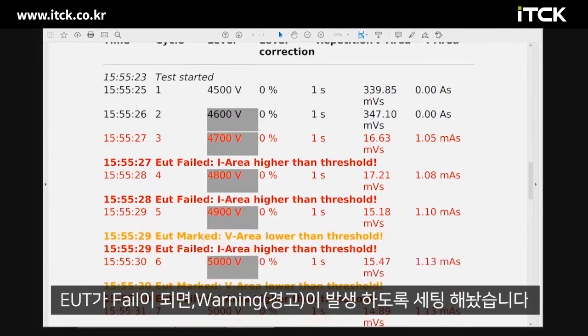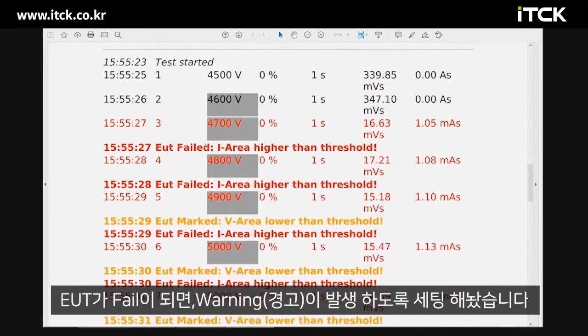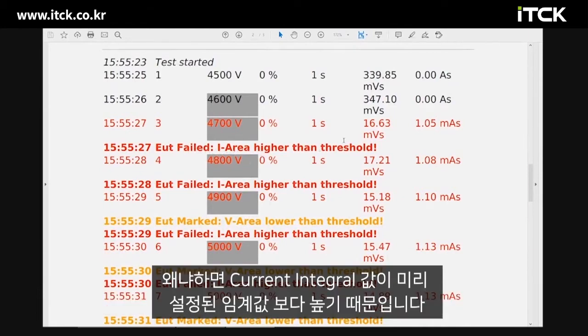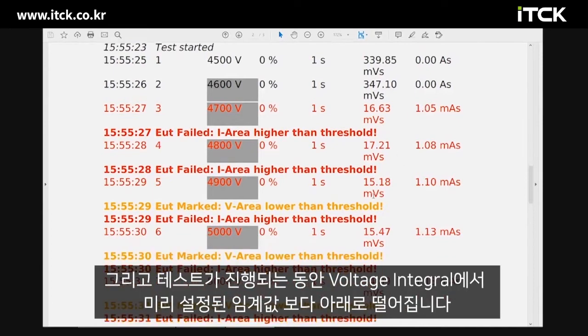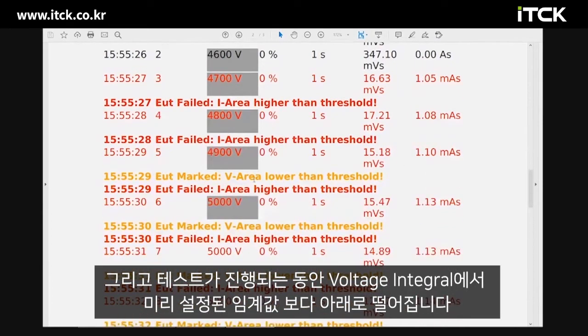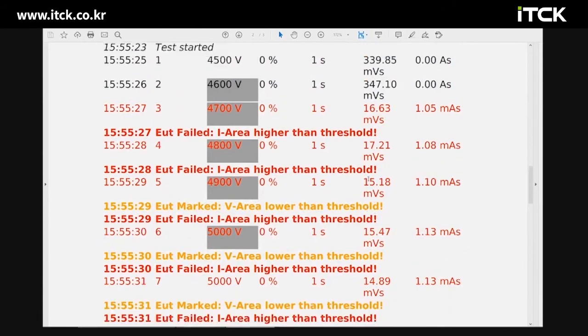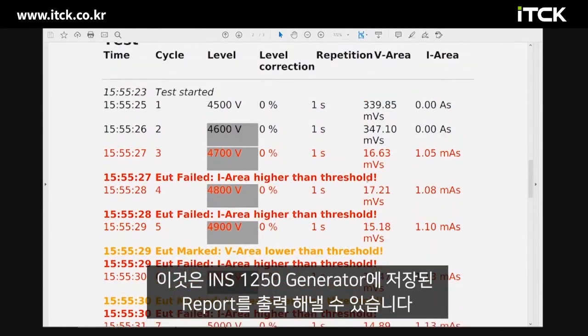We set it so that a warning would be shown that the EUT failed because the current integral was higher than the predetermined threshold. And then when the test progressed, the voltage integral dropped below the predetermined threshold. And this is the test report that we can extract from the INS 1250 generator.